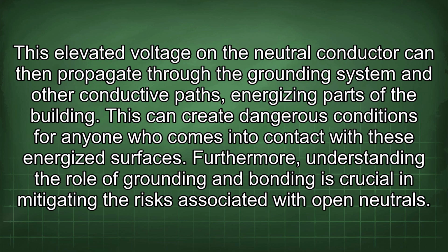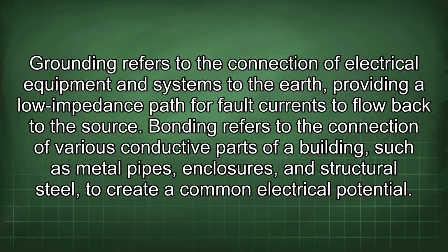Furthermore, understanding the role of grounding and bonding is crucial in mitigating the risks associated with open neutrals. Grounding refers to the connection of electrical equipment and systems to the earth, providing a low impedance path for fault currents to flow back to the source. Bonding refers to the connection of various conductive parts of a building, such as metal pipes, enclosures, and structural steel, to create a common electrical potential.